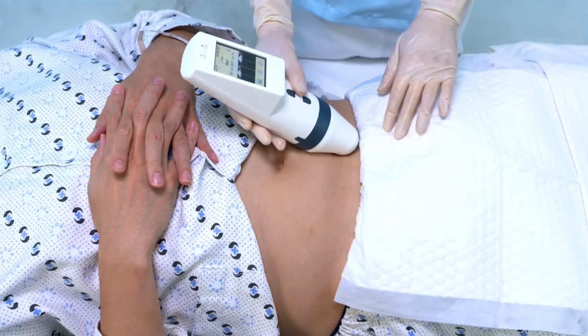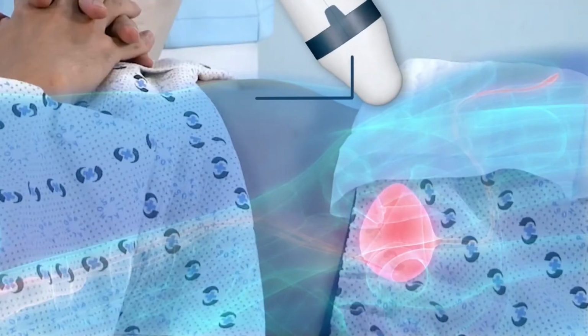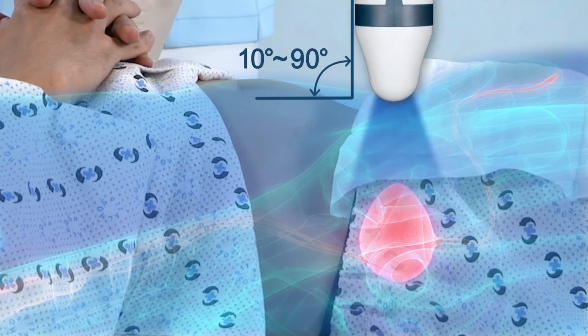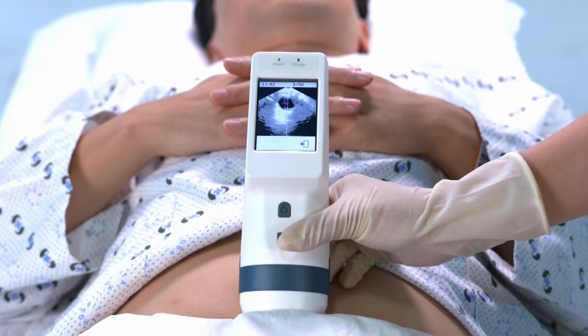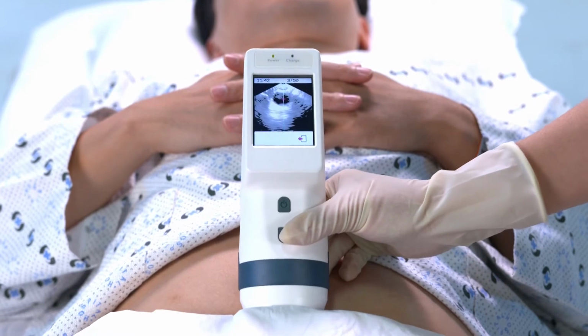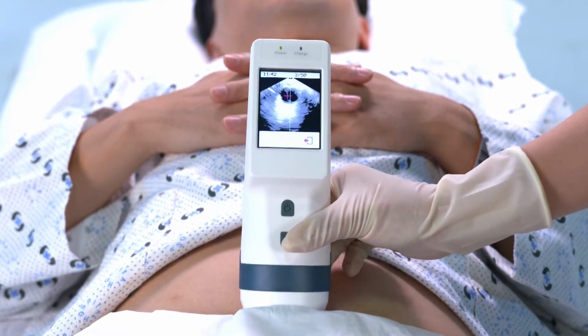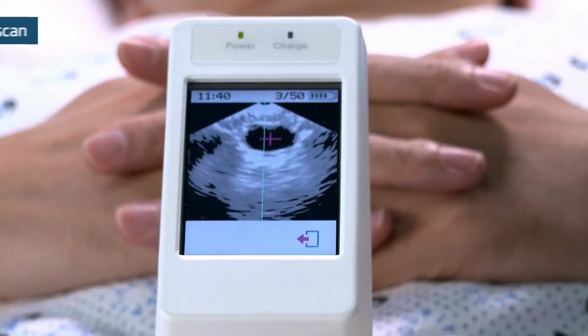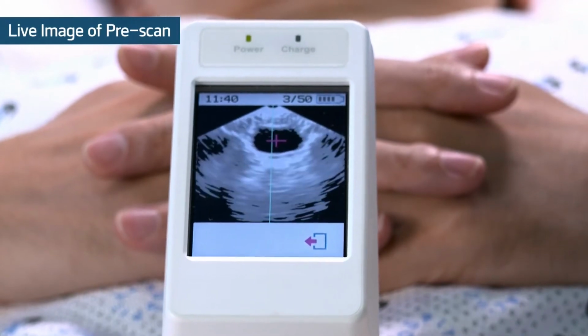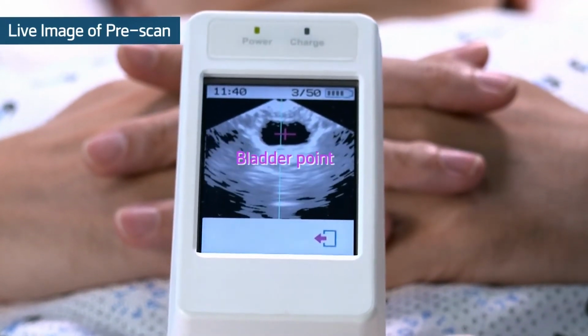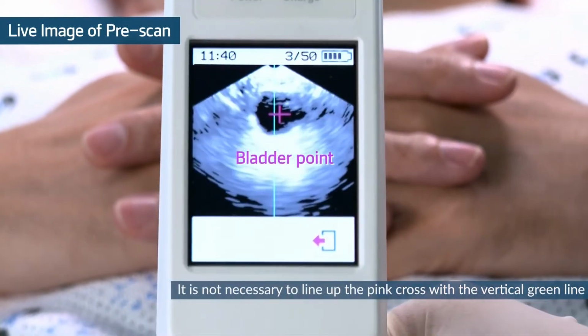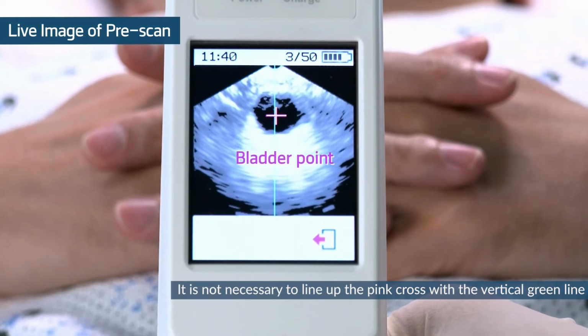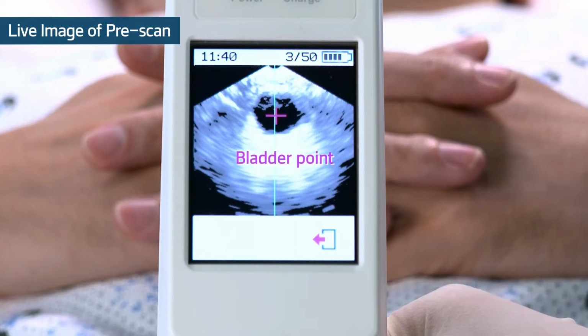Place the probe from the target location towards the bladder and slowly raise it up until you find the biggest area of the bladder. Please make sure the probe is lifted only up to 90 degrees from the abdomen. During the pre-scan, the bladder point and green line will help to get an accurate measurement. Press the scan button again. Hold the probe steady until the scan is completed.